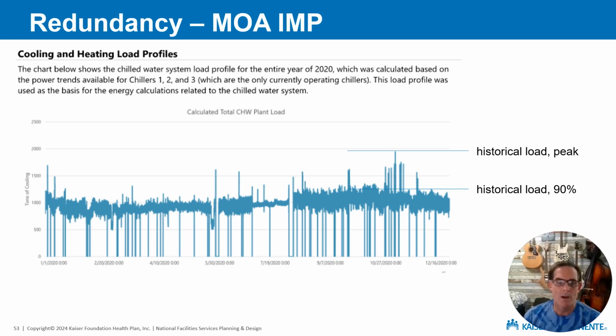And so if we were to lose half of the capacity there, we would probably be able to meet the load in this system a solid 75% of the year. The 90% load is not too much higher than half of the peak load, which is to say that a system that covers 90% of the year is only a fraction of the capacity of the system at the peak load. So with the best of intentions here, we may want to add a third chiller. Oh wow, let's do an N+1 beyond the peak, and that's a level of safety where we're designing for something that is a very rare event in the year.